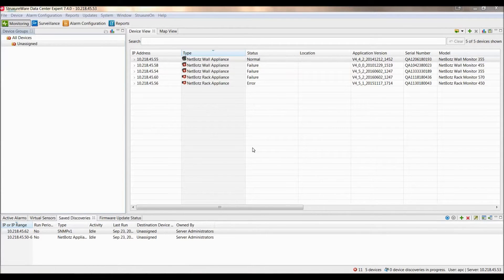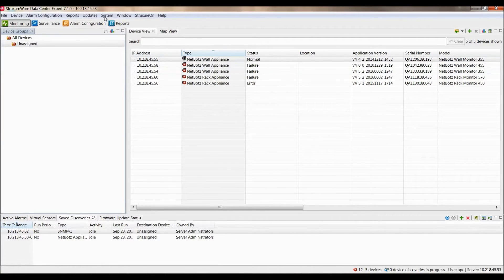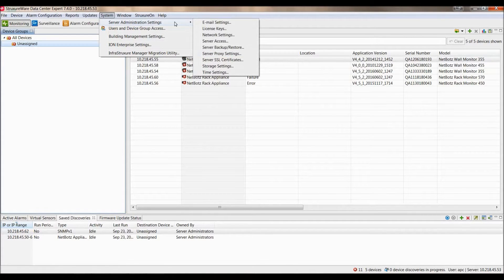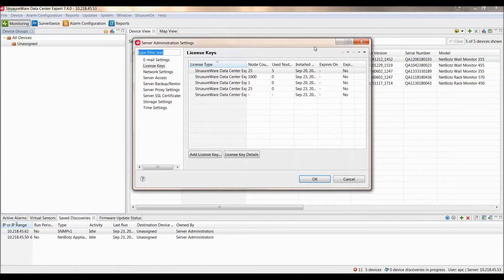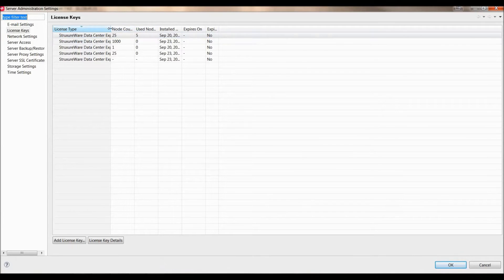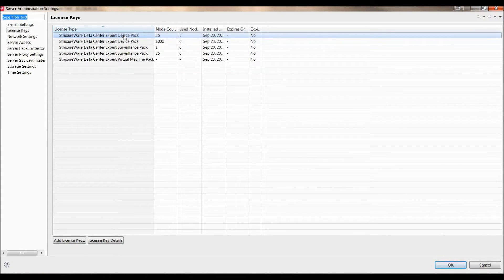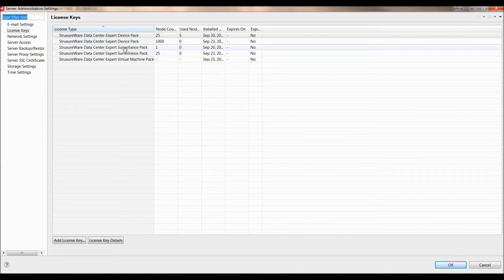Start by logging into the StruxureWare Data Center Expert client. To see how many licenses you have available on your server, you can go to the System Menu, Server Administration Settings, and License Keys. Each NetBotz Appliance that you would like to add into StruxureWare Data Center Expert requires the use of one device pack license, and each subsequent camera that you would like to enable for surveillance requires a surveillance pack license.